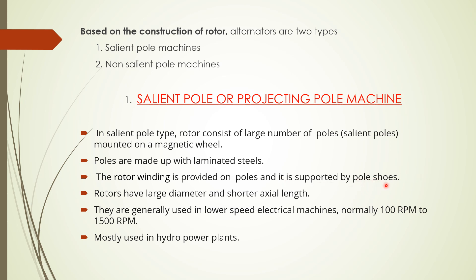The function of the pole shoe is to support the poles and carry the field windings, or simply the rotor windings. The rotor has a large diameter and shorter axial length because it consists of a large number of poles. In order to carry a large number of poles, the rotor must have a large diameter and shorter axial length — this is a very important point for technical exams.